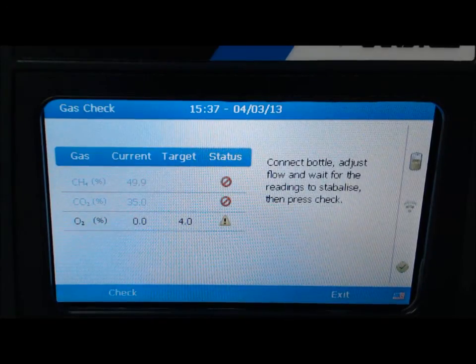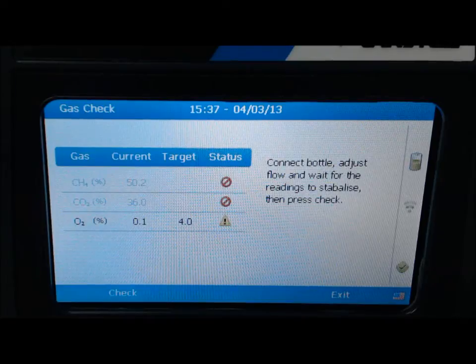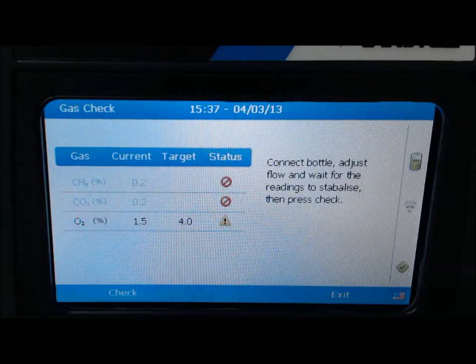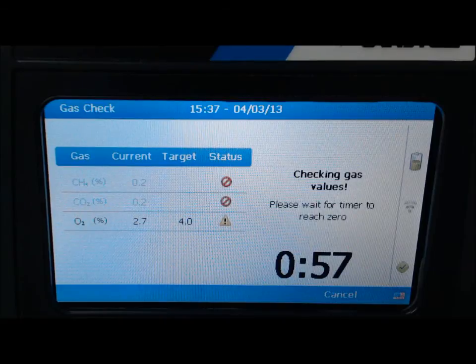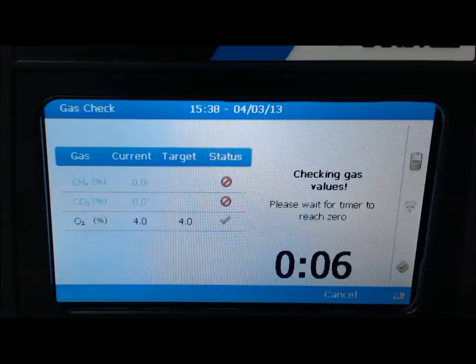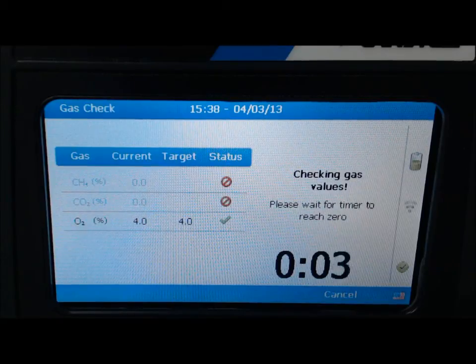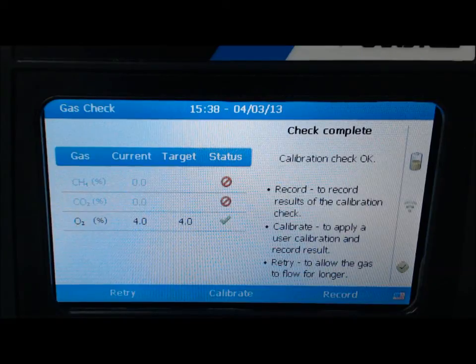At this point, connect the 4% O2 calibration gas mix to the inlet, which is the white colored port on the analyzer. Open the pressure regulator for gas to start flowing and select check when readings have stabilized. A 1-minute timer will start for readings to stabilize. When the timer reaches zero, the following message will be displayed: Check complete. Once again, read the status field and select calibrate to span O2.